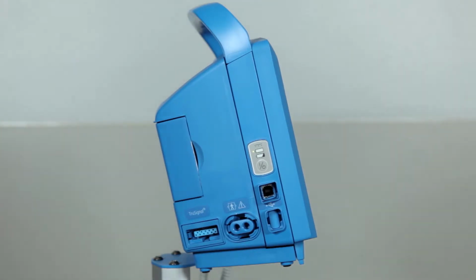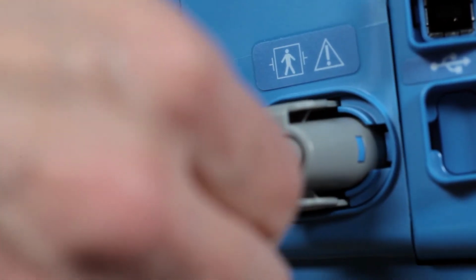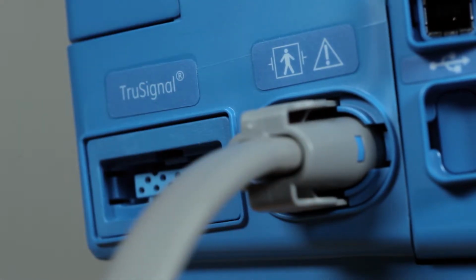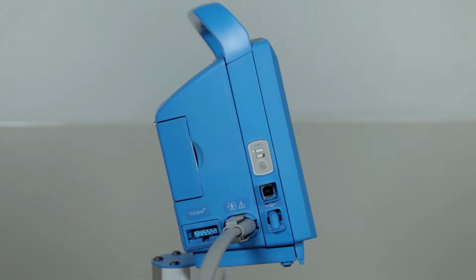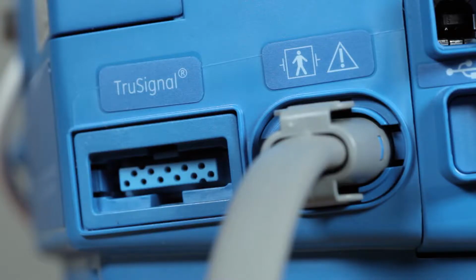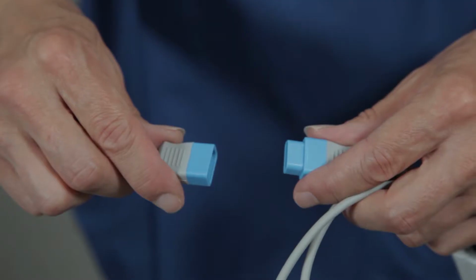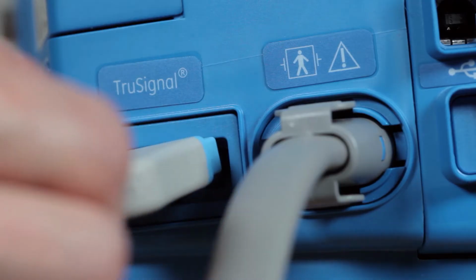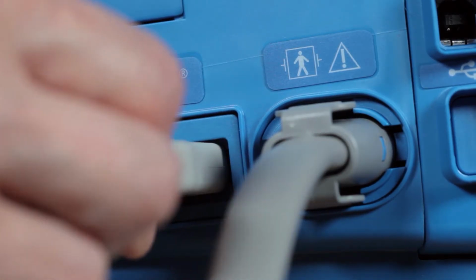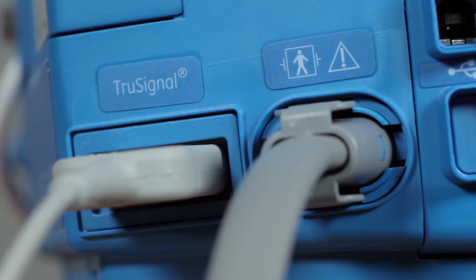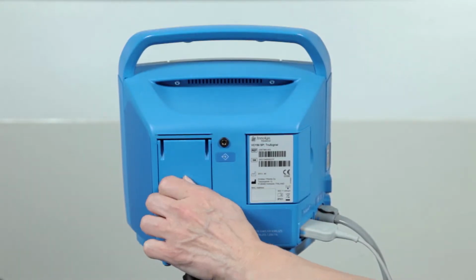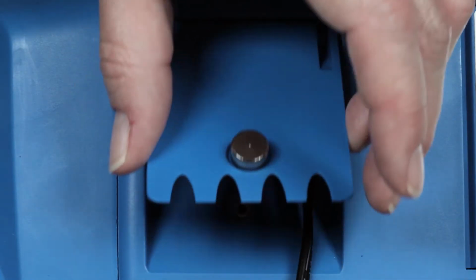First, we will connect the non-invasive blood pressure hose. Connect the end of the air hose with quick-release clips to the non-invasive blood pressure connector on the left side of the monitor. Next, we'll connect the SpO2. This connector is also located on the left side of the monitor. Depending on the sensor type, plug an oxygen saturation sensor into the extension cable or directly into the monitor. If the barcode reader is to be used, connect it to any USB port in the back of the monitor.